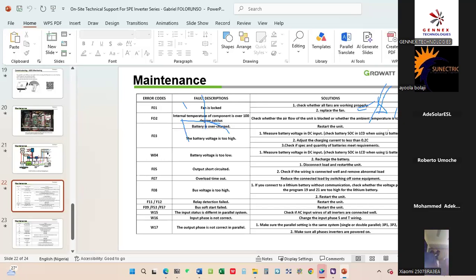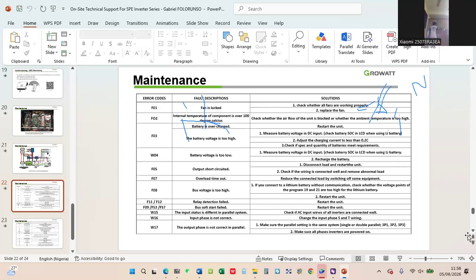Either because of poor ventilation or some other issues, you get F01. Another one is F02, which is abnormal temperature, and we've seen so many cases that F01 and F02 are almost brothers and sisters. We've seen situations whereby the installation site is not good enough for the inverter, but it's forcefully installed there, because customers don't really care about the output or the lifespan and experience of the inverter.